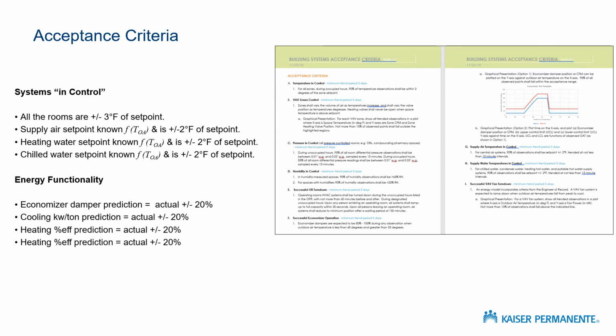And again, the heating hot water set point or the chilled water plant set point should be pretty well known. It's generally a function of outside air temperature or maybe outside air temperature plus a couple of other variables. And whatever set point we are striving for, we should be there. We should be plus or minus 2 degrees of whatever that set point is.